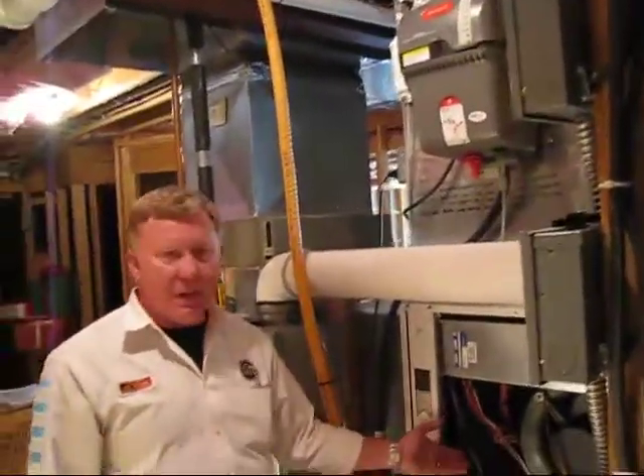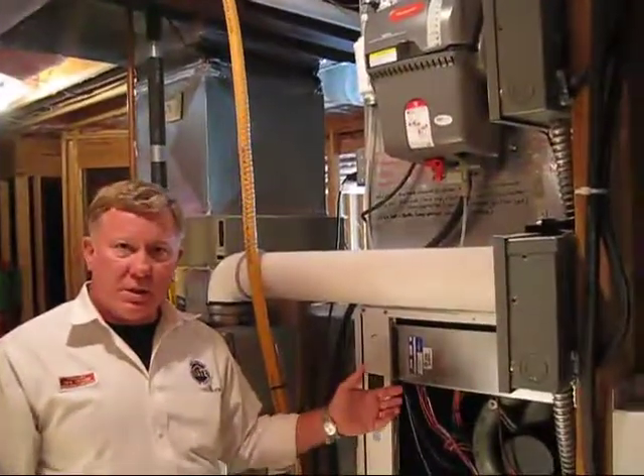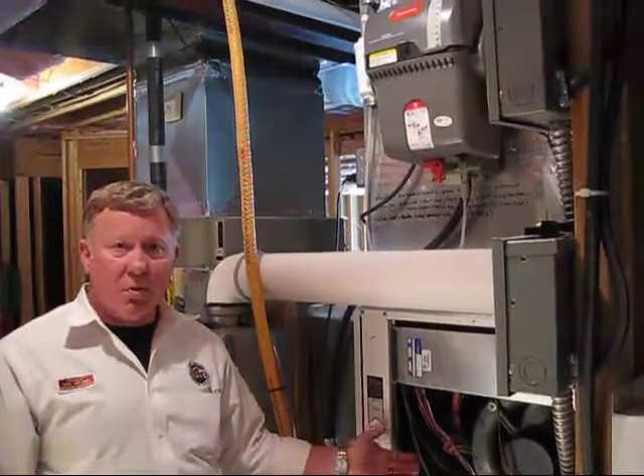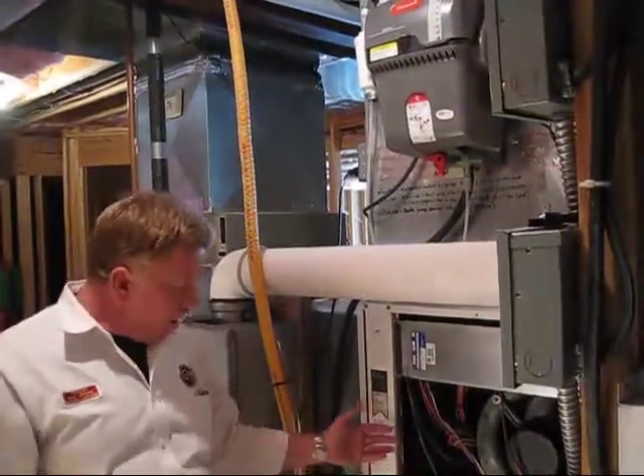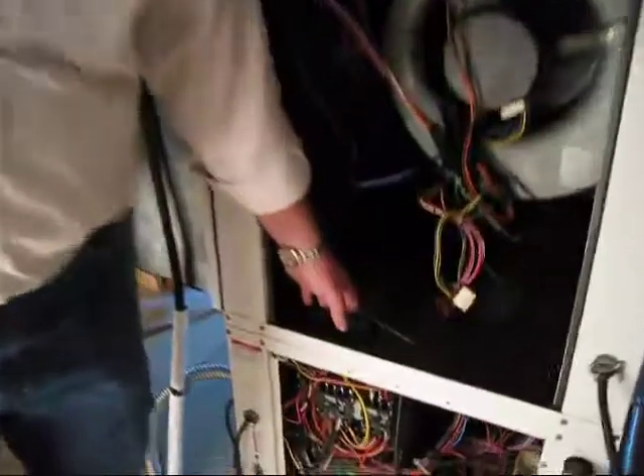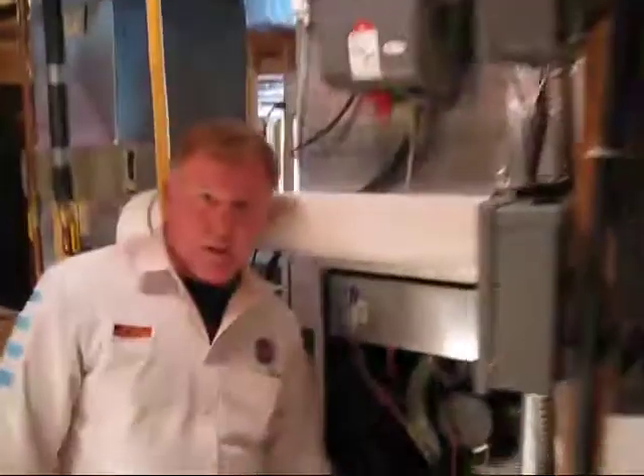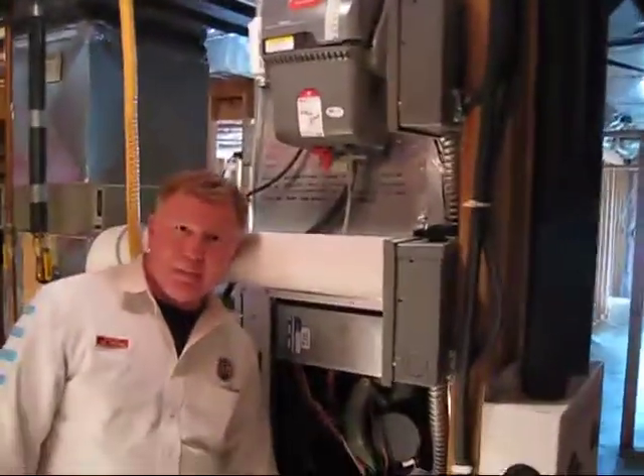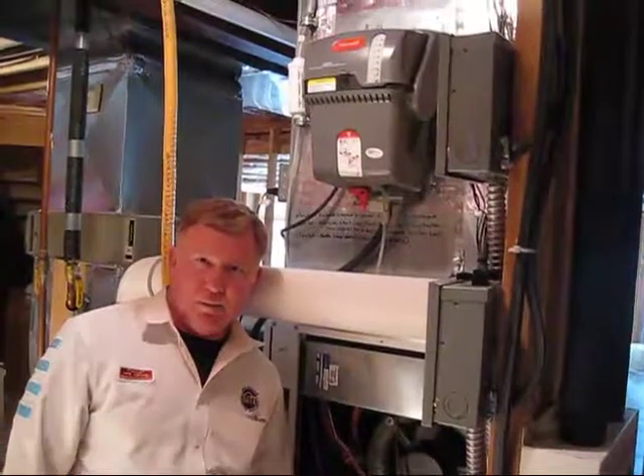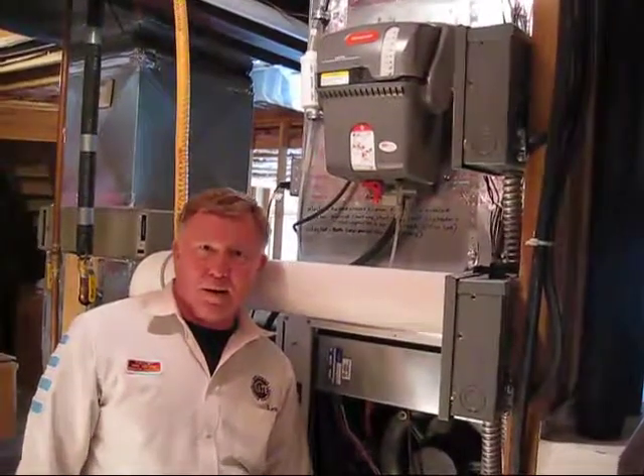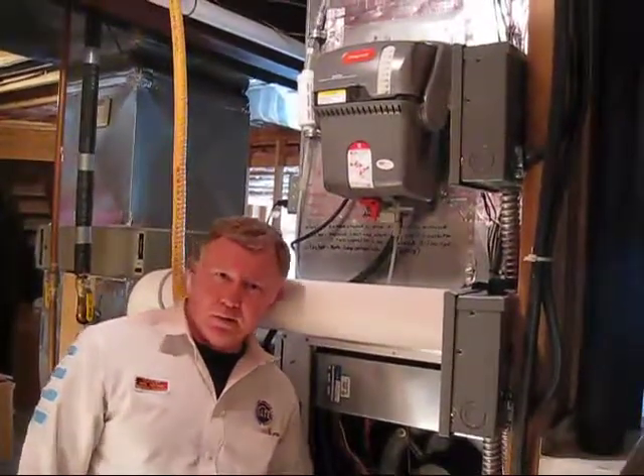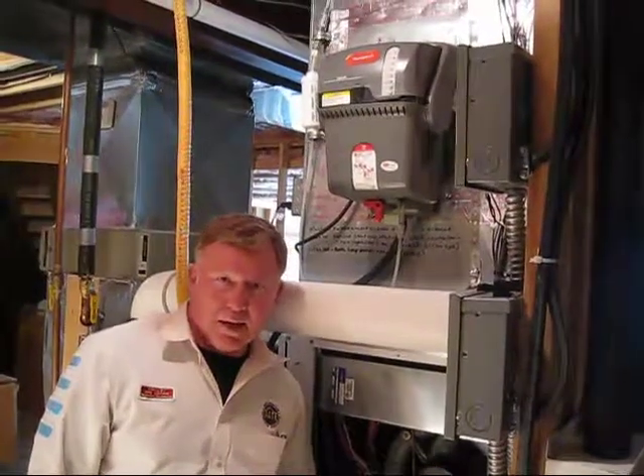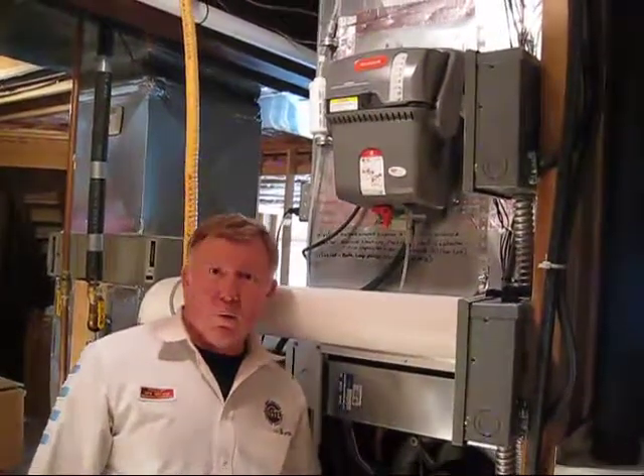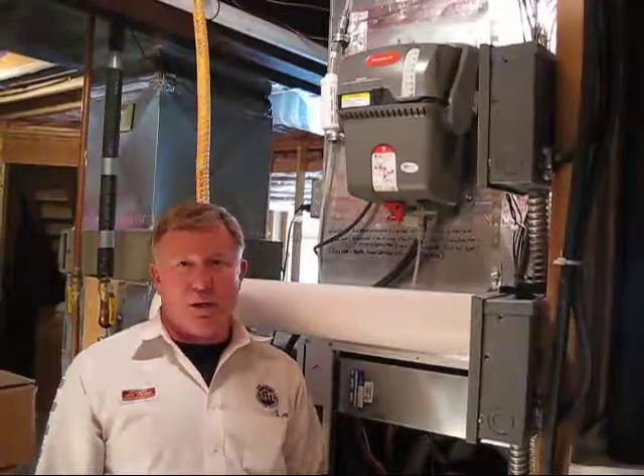But a piece of equipment like this one, which is a geothermal, ultra-high efficient piece of equipment, also has a condensate pan within the unit that you cannot simply wash out or rinse out. It has a special sensor in it, and if it's not properly cleaned, something as simple as a spider web can cause this equipment to fail and not operate until someone comes out and checks it. It will think it's full of water when it is not. It's a very simple thing, easily missed.